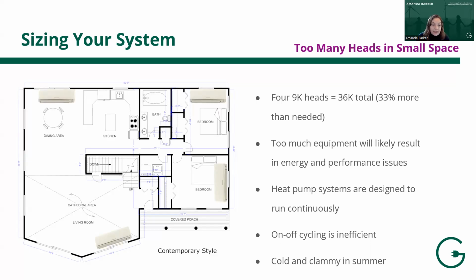Now, this is the sizing that we want to warn you about. Too many heads in a small space. So let's say that a contractor comes in and says, oh, your heat load is 24,000 BTUs, but you need a head in every room. So let's say they put in 4 heads at 9,000 BTUs in each room. And they basically say, yes, this gives you a maximum capacity of 36,000 BTUs, which is more than you need. But it's fine because you can just run them less. But you've now got 33% more heating load than what you need.